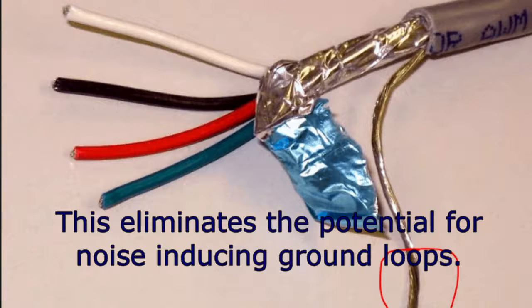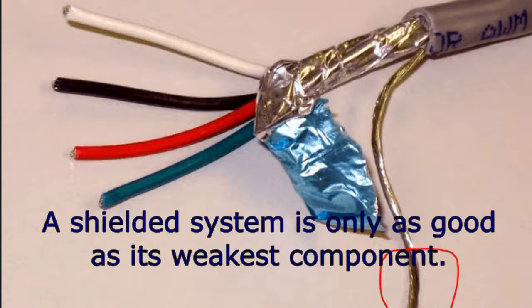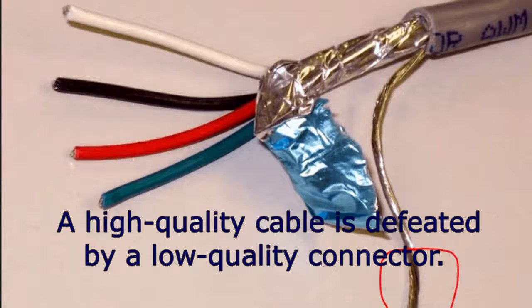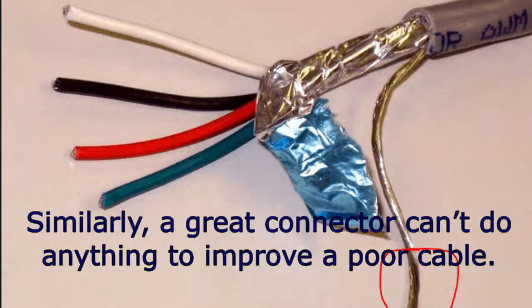Five, ground the cable at one end. This eliminates the potential for noise-inducing ground loops. A shielded system is only as good as its weakest component. A high-quality cable is defeated by a low-quality connector. Similarly, a great connector can't do anything to improve a poor cable.